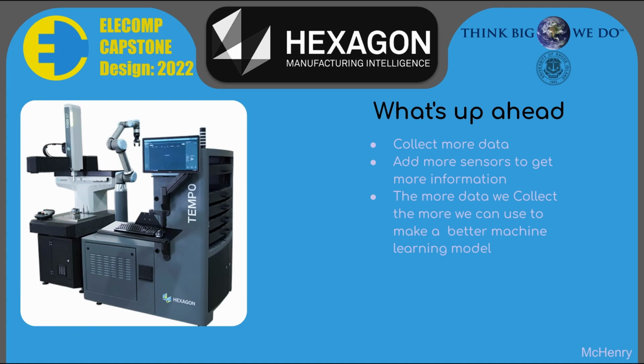Other things we'll be doing is getting an accelerometer to add to the machine. Currently there are accelerometers on the machine, but we don't think the current locations give us enough data, so we'll add another one to see how the forces affect probe decalibration. In addition to this, we're also going to be adding more probes than we're currently using, just to see if there are any differences in deflection, temperature, and other environmental variables.